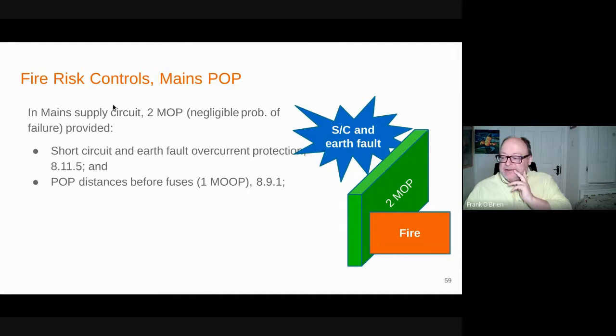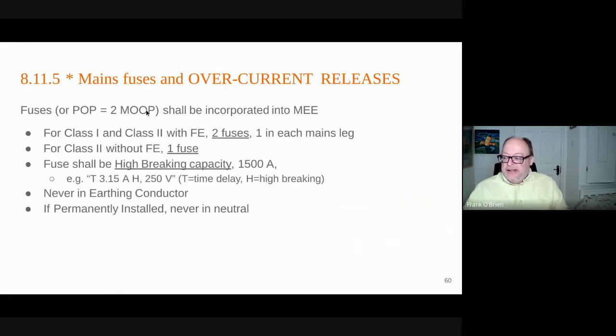the other thing is fusing's nice. So in fact, the standard requires fusing for short circuit protection. And so we sort of saw in the mains that pop thing and for ground faults and short circuits. And so that's the 811.5 that talks about that. The thing I'd mention is this high breaking capacity. There's a 1500 amp rating on H fuses. These are IEC fuses. And so if you're in the mains, you have to have an H rating, so be careful.